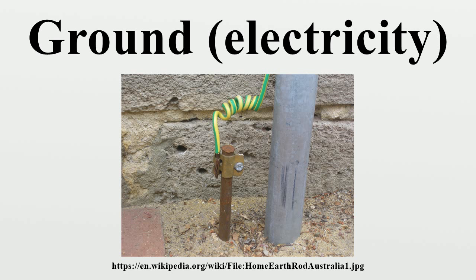On an HRG system, a sensing resistor is used to continuously monitor system continuity. If an open circuit is detected, the monitoring device will sense voltage through the sensing resistor and trip the breaker. Without a sensing resistor, the system could continue to operate without ground protection and transient overvoltages could occur.